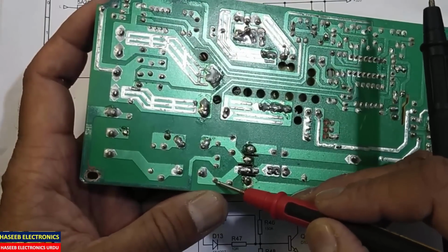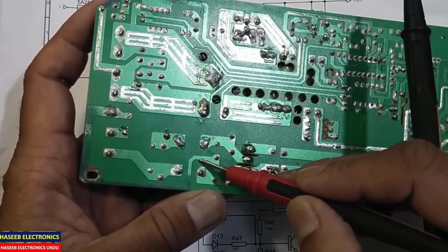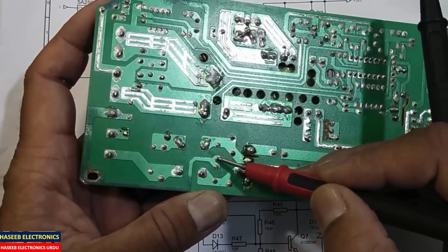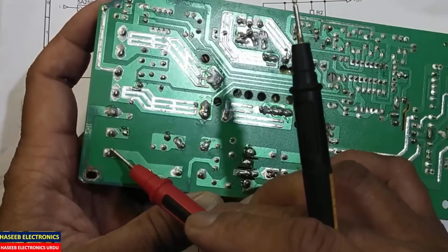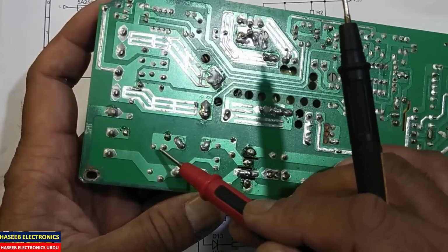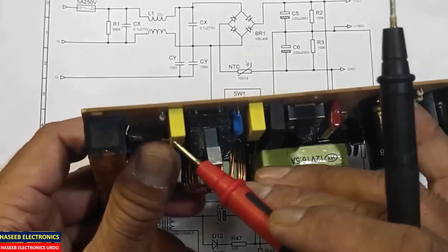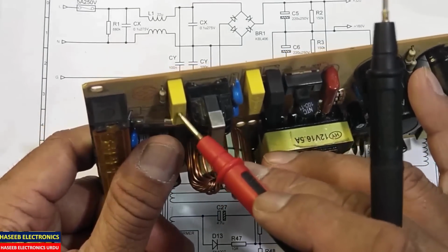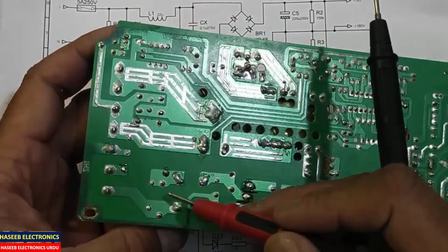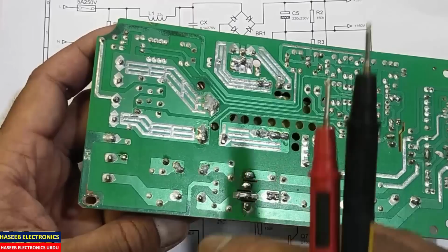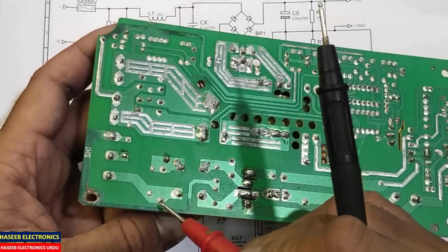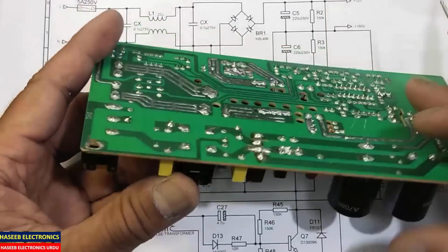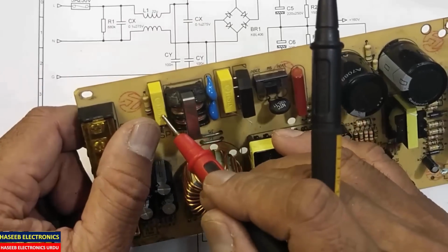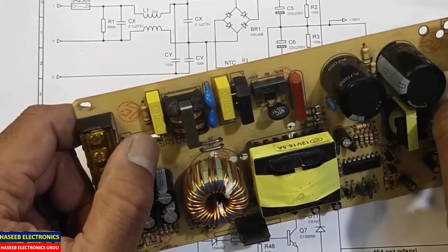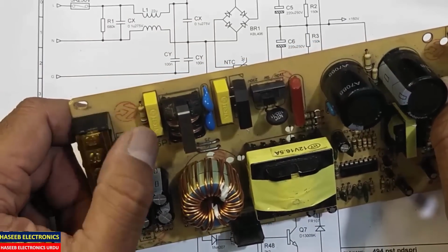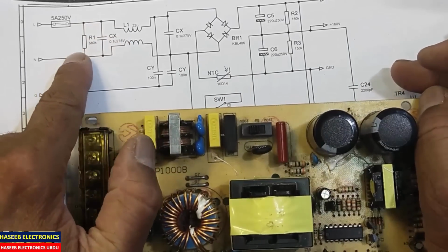A blue capacitor is connected between line and earth/chassis, and neutral and chassis. If there is high frequency over-voltage noise, this capacitor becomes short circuit, its internal impedance decreases, so if continuous strikes arrive in the input line, this capacitor heats up and causes overcurrent to flow from line to neutral internally.